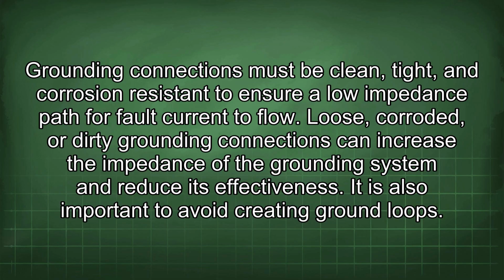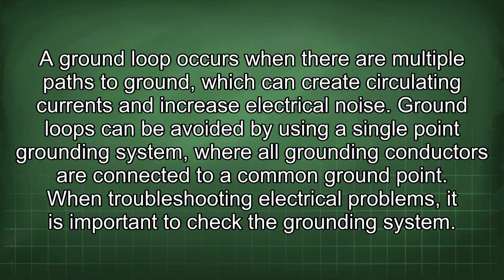It is also important to avoid creating ground loops. A ground loop occurs when there are multiple paths to ground, which can create circulating currents and increase electrical noise. Ground loops can be avoided by using a single-point grounding system where all grounding conductors are connected to a common ground point. When troubleshooting electrical problems, it is important to check the grounding system.